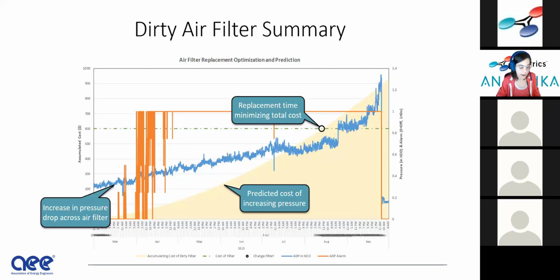The optimal point is going to be a time that minimizes, right, your total cost. So there's a cost to running your fan at increased pressure. You know, you're having to overcome that differential pressure. Your fans are going to work harder. But that's what this yellow line represents. And I've seen presentations where people talk about this air filter optimization, but you're waiting until the cost of that dirty air filter reaches a point that you've determined to be optimal. And then you're going to say, replace your filter here. So you can see in this chart, the customer, the delta P increases. You see them repair it right here. After repair, we see, oh, you can't see my mouse. After repair, we see this differential pressure in blue go back down to set point. It's at about 0.2 inches, water column.